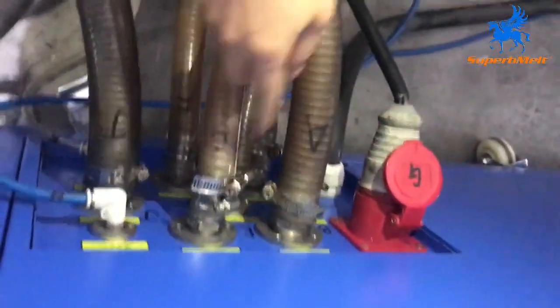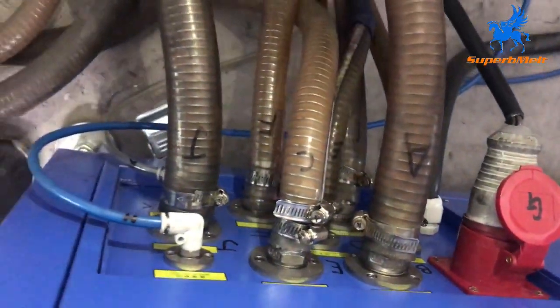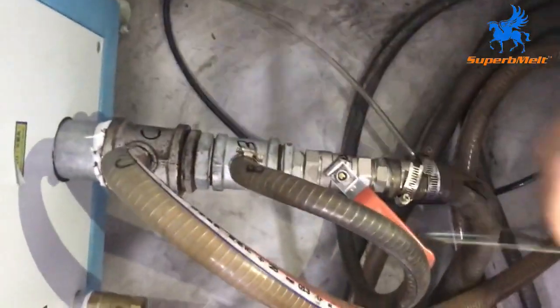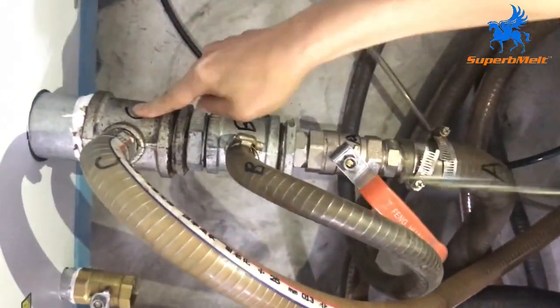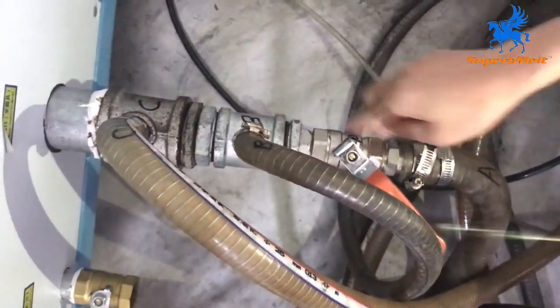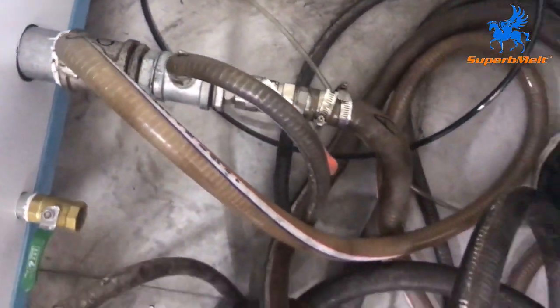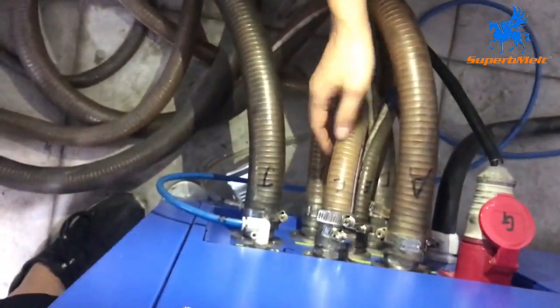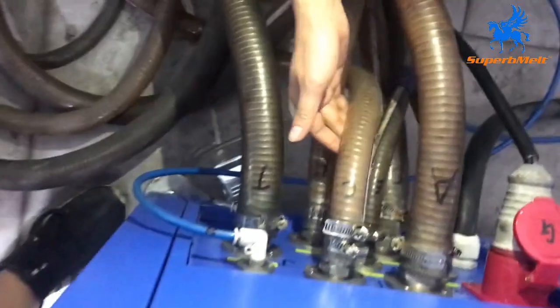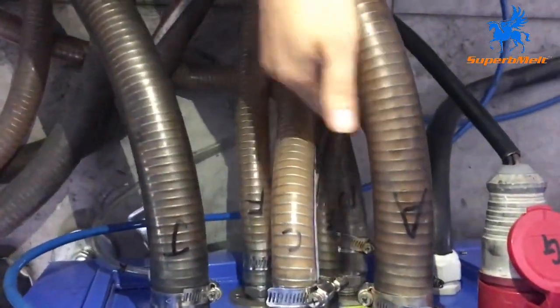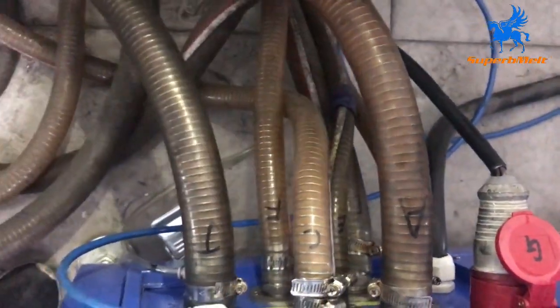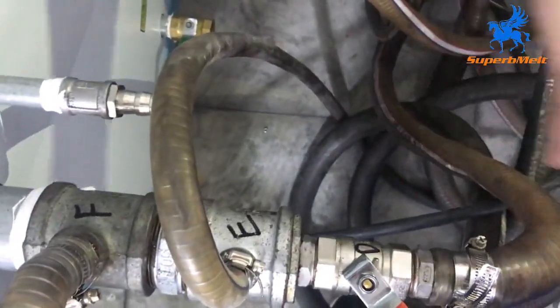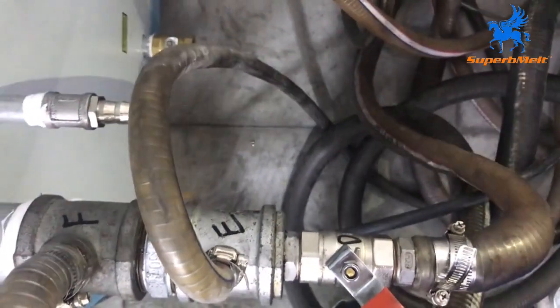There are three water inlets, A, B, C. Three connections. It's water inlet. Water inlet is connected here. It is chiller's water out. There are also A, B, C. You just follow the number, connect the machine. We already mark all the numbers in the machine. This is water inlet. And there are three water outlets, E, D, F. E, D, F is connection chiller here. Chiller here is back to the chiller. So that's the water connection, six lines.